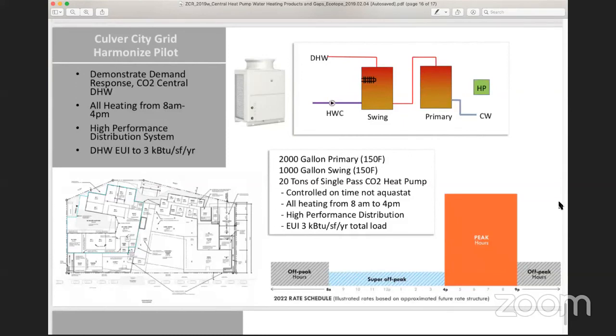Here's a little project we have going on in the LA area, Culver City, and this is a 100-unit senior housing project. We're working on the MEP design for it, and in this specific pilot, we're going to demonstrate a demand response CO2 central DHW system. So we'll set it up to do all the heating between 8 and 4 p.m. We'll also install a high performance distribution system, and so the goal is to get the EUI of the DHW heating to 3 kBtu per square foot per year. Preliminary sizing has shown about a 20-ton single pass CO2 heat pump with some fancy controls, a 2,000-gallon primary storage, and a 1,000-gallon swing tank. So that's a project. This will be installed in 2021, or at least that's the intended schedule. So we'll see how that goes.